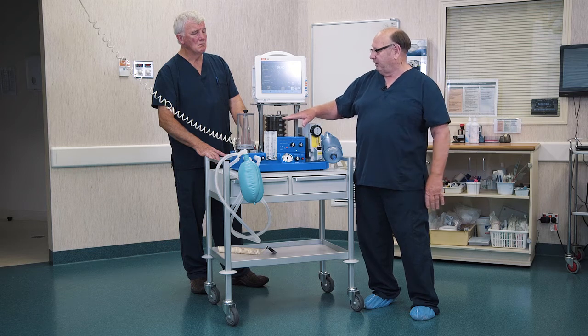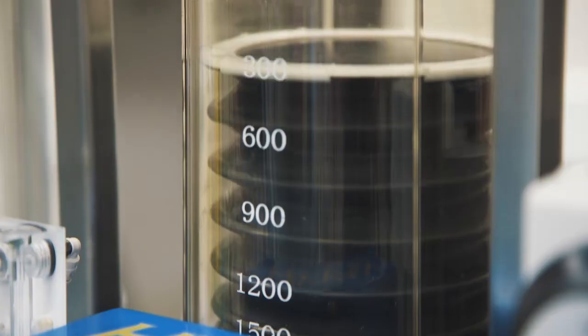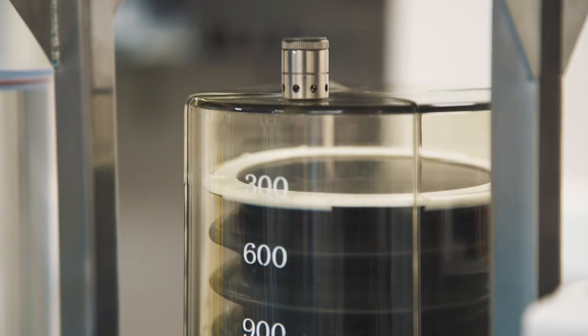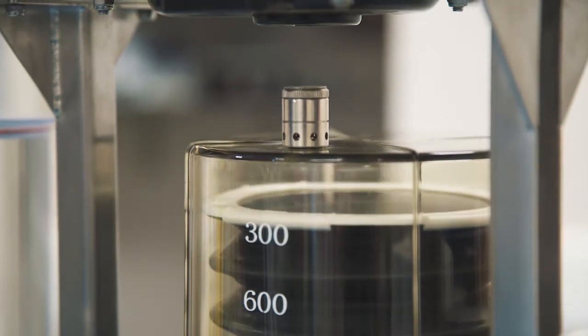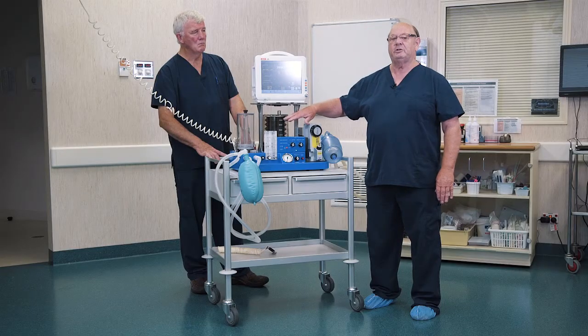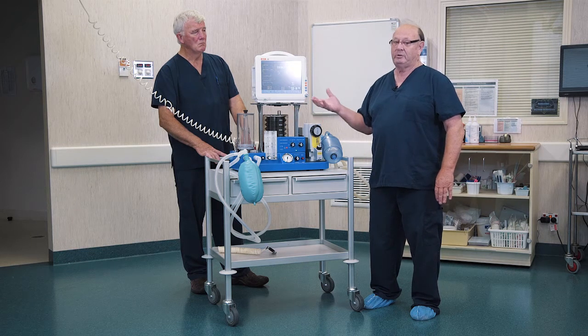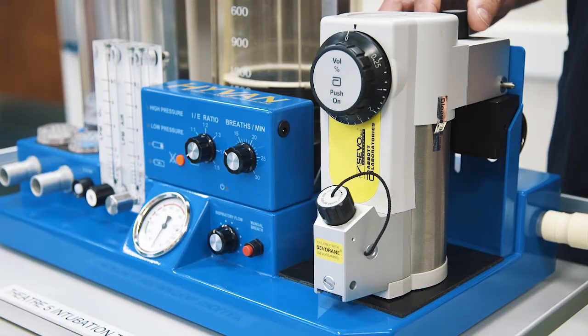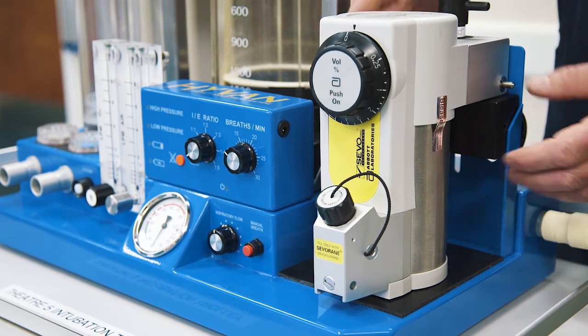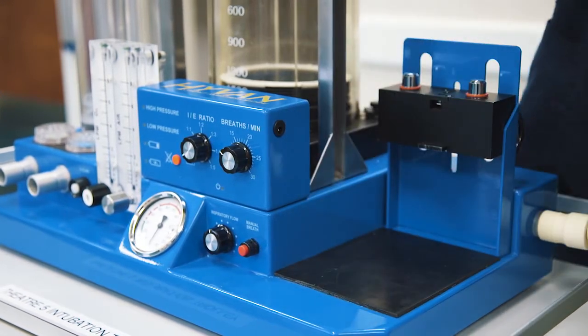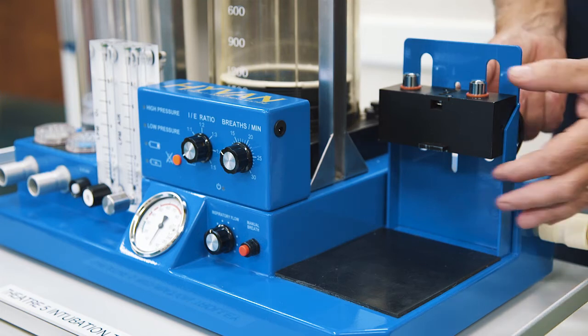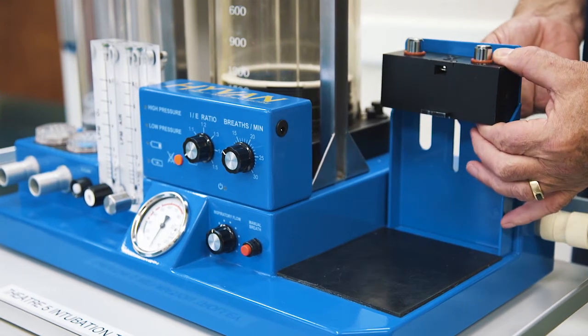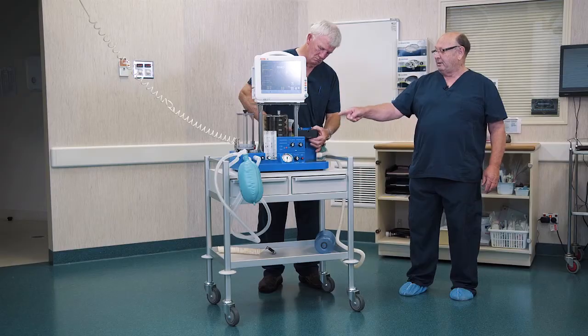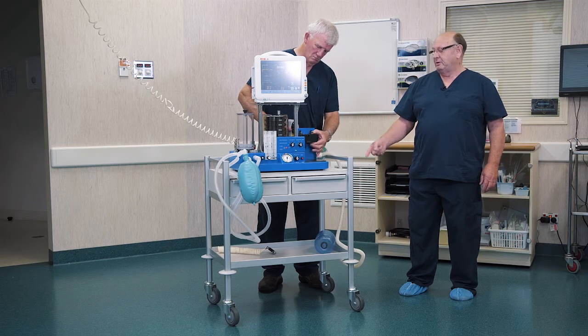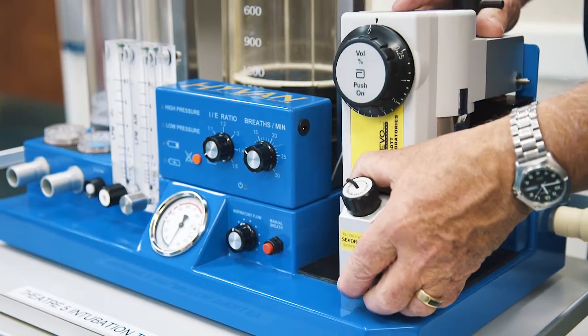And also, if you are short of oxygen, you can connect the bellows drive to air. So you can just use compressed air to drive the bellows and just use oxygen for the patient. That will save you some oxygen in places where it's not freely available. The Selectatec system is just a standard BOC Selectatec system which you can take off. You can put different vaporizers on this machine. Some of them are at different heights, so our Selectatec block can move up and down to suit the vaporizer that you have.